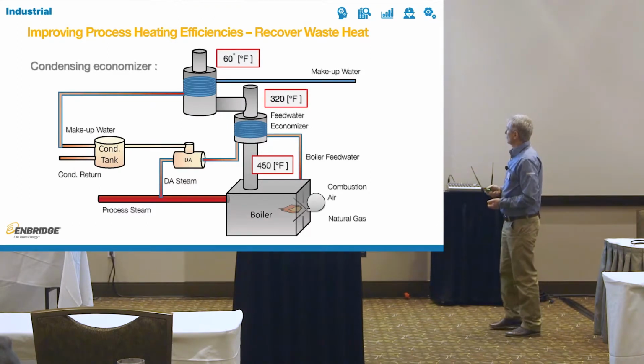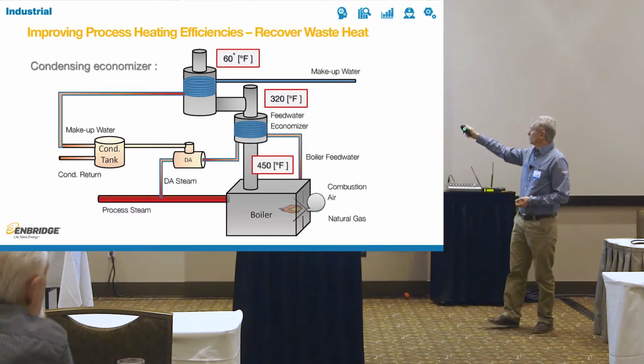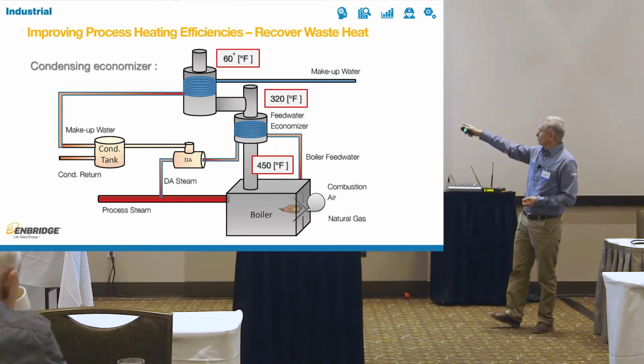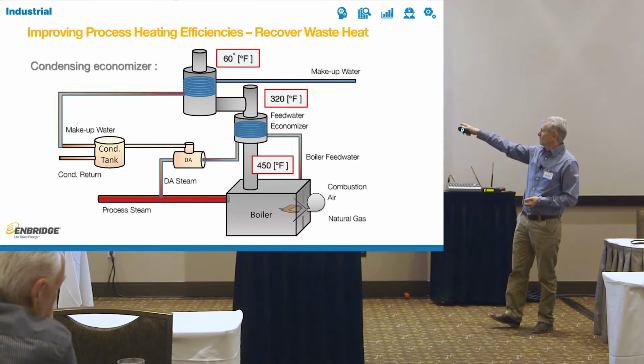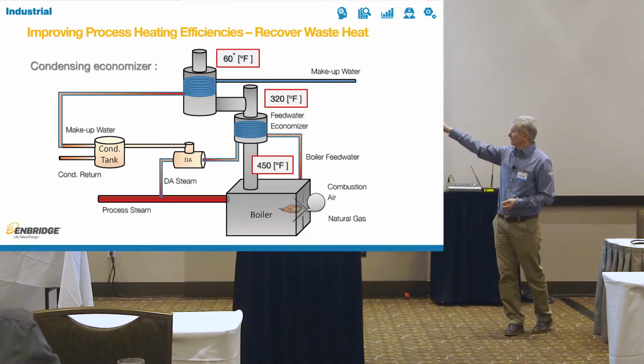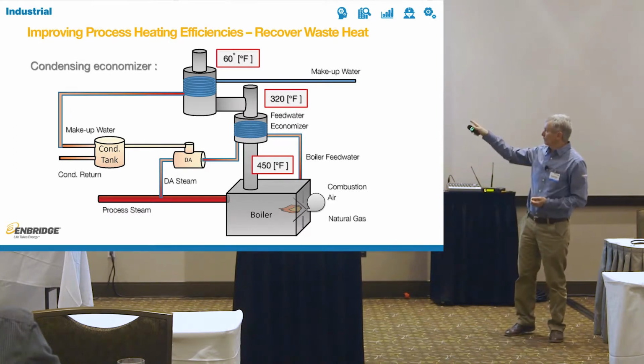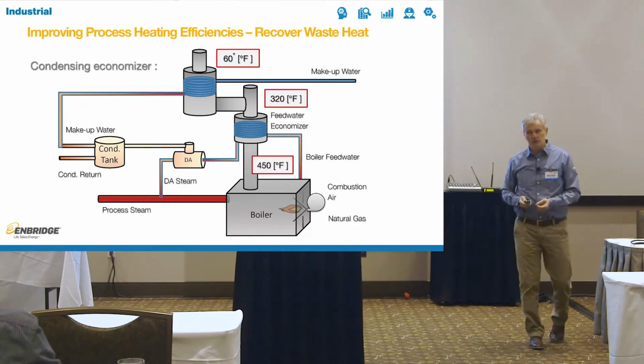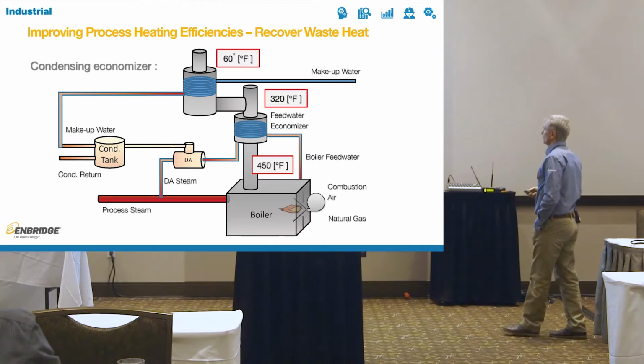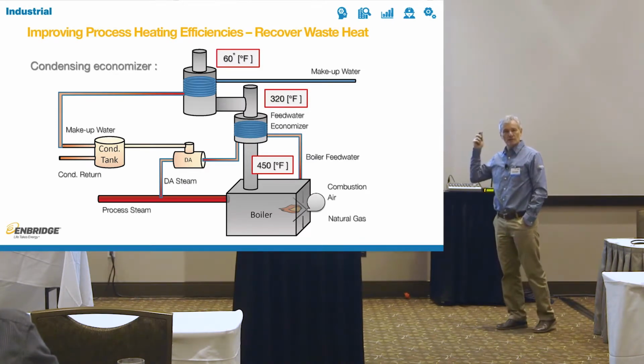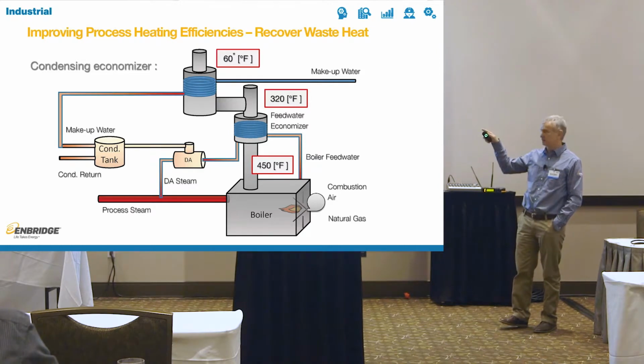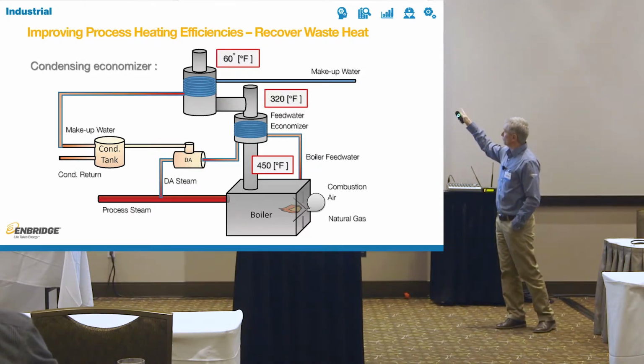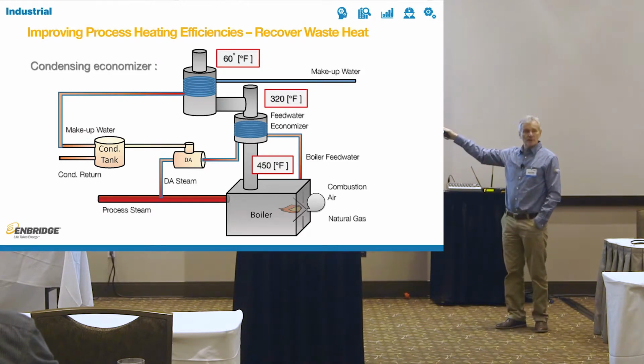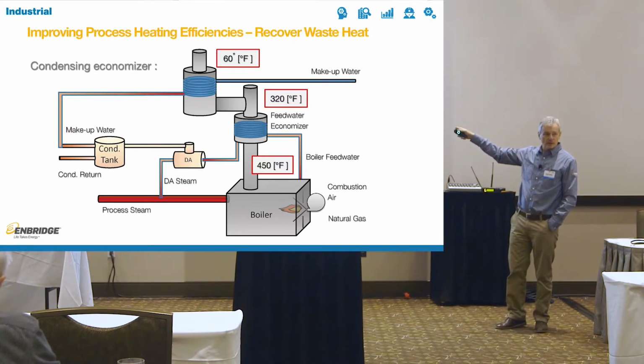So if you look at a condensing economizer, this is a typical boiler room, a very simple one. You have the Feedwater Economizer already. You're using it to preheat the feedwater. It goes back to your deaerator. You have a condensate tank that mixes makeup water and condensate return. The more makeup water you have, the more energy you have to put into your DA, which means the less efficient your system is. So now we can put a condensing economizer on top of the Feedwater Economizer. Once the flue gas leaves the Feedwater Economizer, it goes into the condensing economizer, and you can put cold makeup water through it and put it back into the condensate tank at the end, preheating your makeup water.